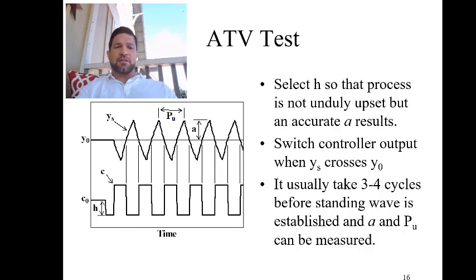And so we do this for a few cycles until we have a standing oscillation shown here. So when we have a standing oscillation we can then use the values. We have our H value which is the change in the controller output. We have the value shown here A which is the amplitude of the oscillation. And then we have this value PU which is the period of oscillation that was established.